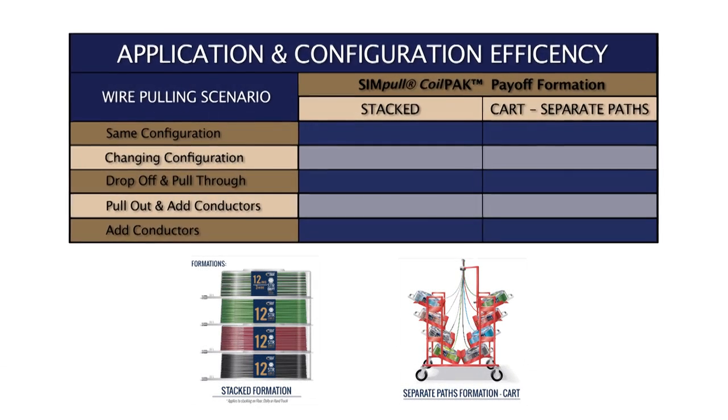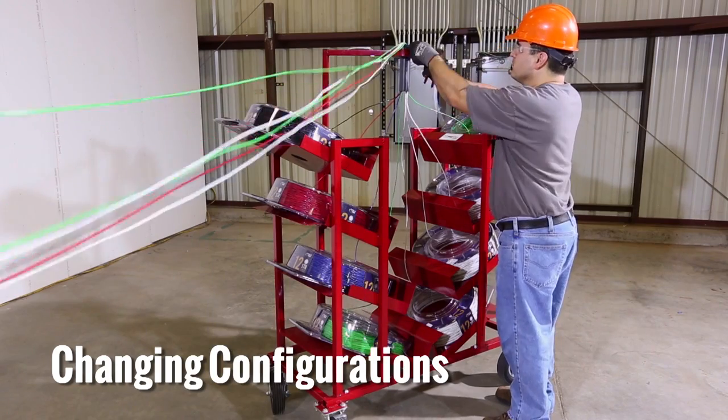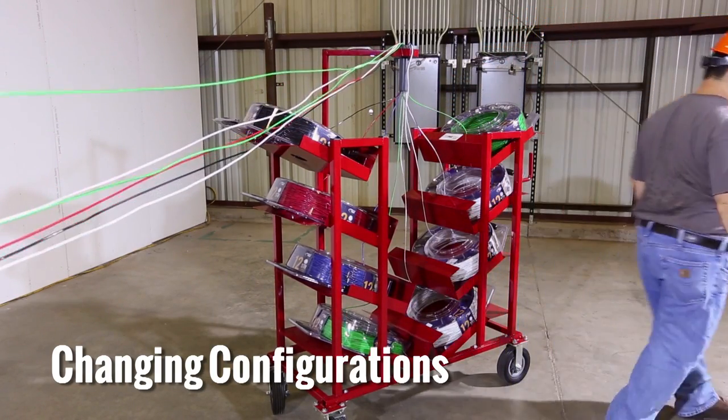For pulls that require frequent changing of conductor quantity or color, the separate pathways provided on the SIMpull CoilPAK cart are the best option. The SIMpull CoilPAK cart speeds up the process of changing out or adding conductors from pull to pull, and prevents individual conductors from twisting or tangling with each other.